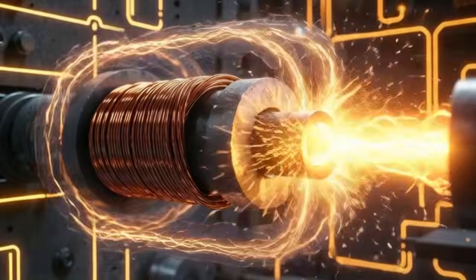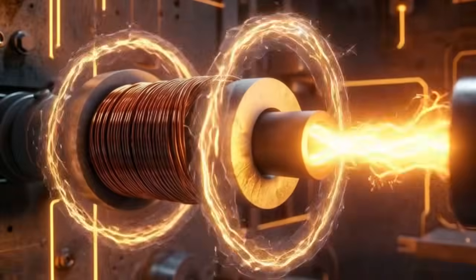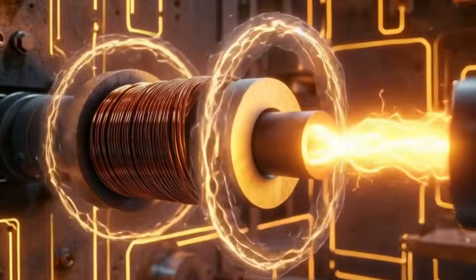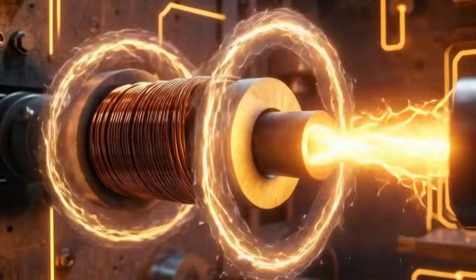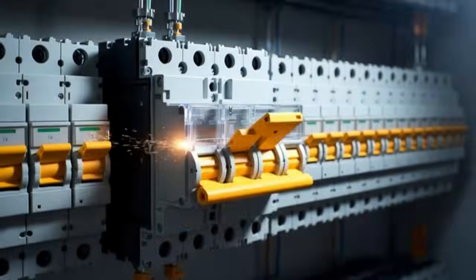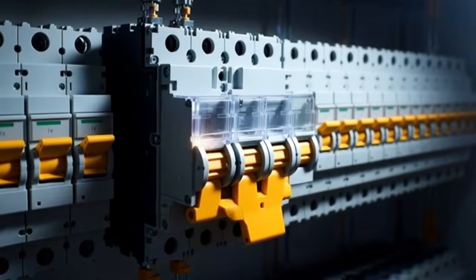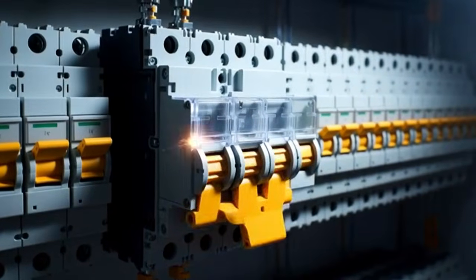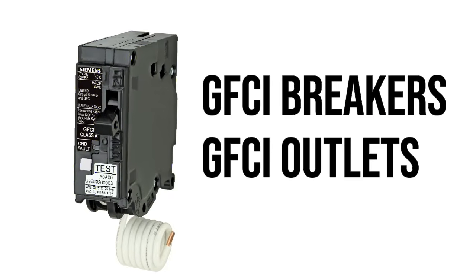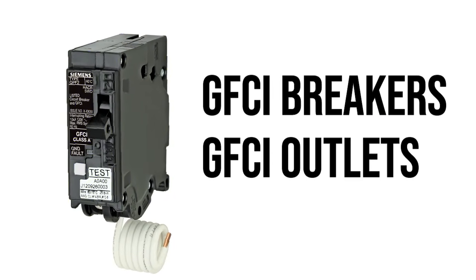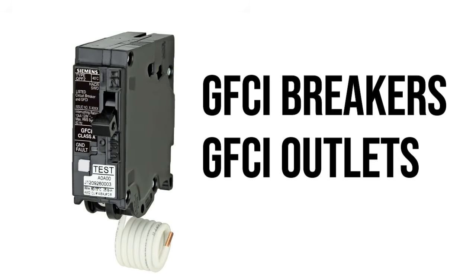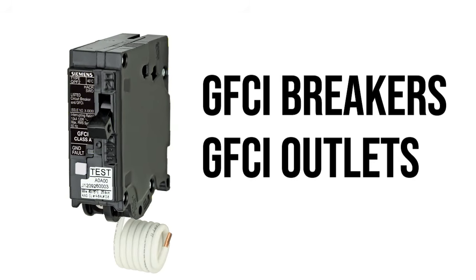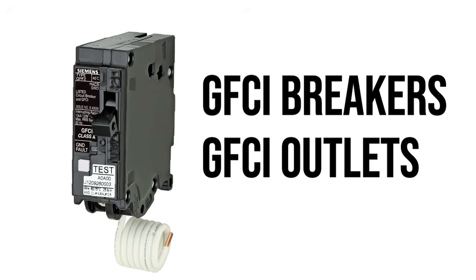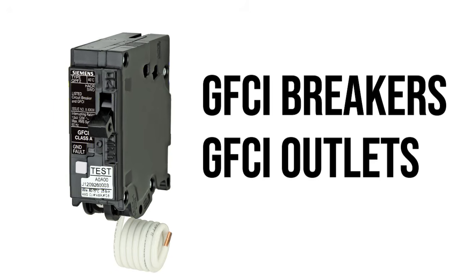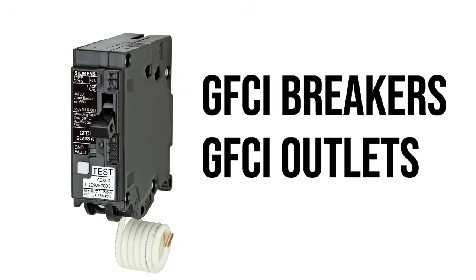When a ground fault occurs, current flow becomes unbalanced. More current flows out on the hot wire than returns on the neutral. The breaker detects this imbalance and trips. If you have GFCI breakers or GFCI outlets protecting the circuit, they're designed specifically to catch ground faults. A GFCI trips when it detects a current imbalance as small as 4 to 6 milliamps, far below what would trip a standard breaker.